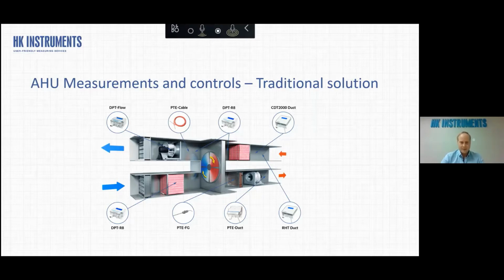The fans you can measure with the differential pressure, and with this kind of calculation you can get the airflow rates directly based on the differential pressure. And the filter clogging you can sense with the pressure difference. And also this control strategy called duct static pressure control. You need to have a pressure transducer to maintain the designed static pressure.